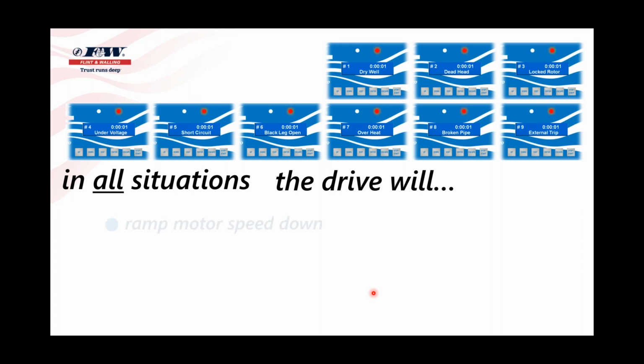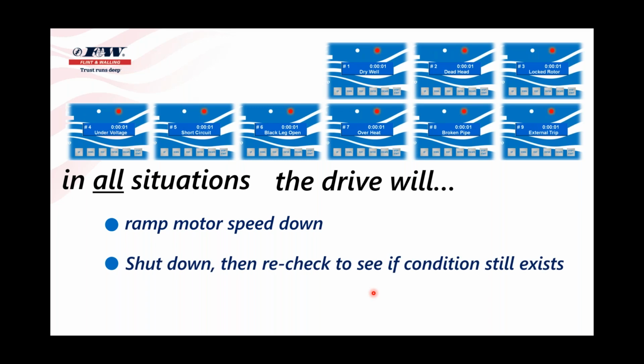So in all situations, the drive's going to ramp the motor speed down. So if things are heating up, it's going to ramp the speed of the motor down automatically to allow things to cool down a little bit. And if need be, it'll shut down. But once it shuts down, it's going to come back on and recheck to see if that condition still exists. That doesn't take very long, and it'll do it, I think, 3 times.